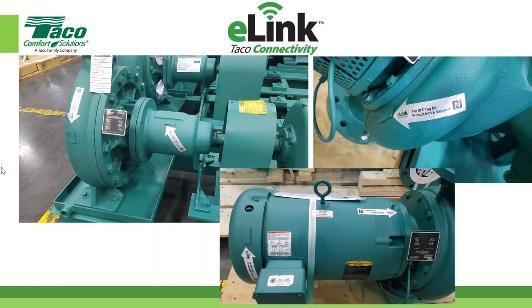So here's that eLink. We mount two tags on the FI and CI pumps. One is on the pump, as you can see over here, right? And you can see it gets painted over, but that's okay. And another is either on the bearing frame or the motor. Sometimes we put it on the motor, sometimes we put it on the bearing frame. And we have this note right here as well, as you can see. So you need to take your phone, right? An iPhone, I forgot what level you need. And these tags have near field communication, NFC.